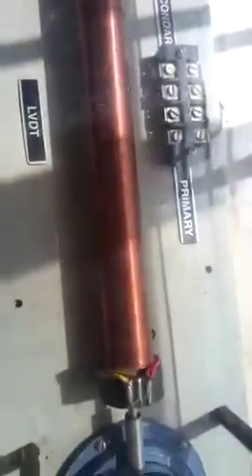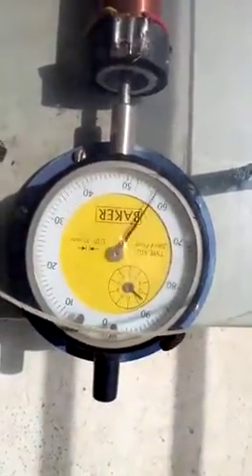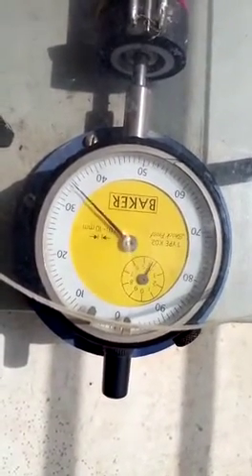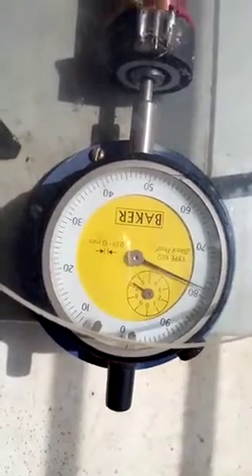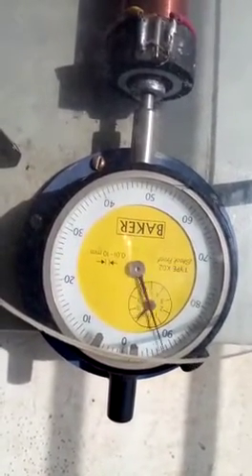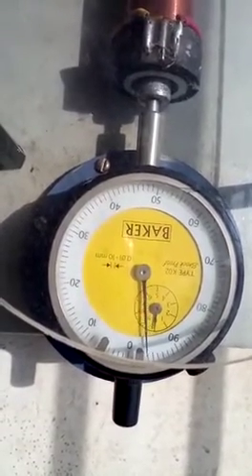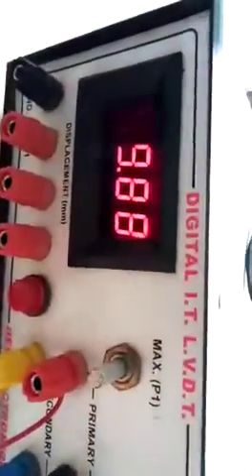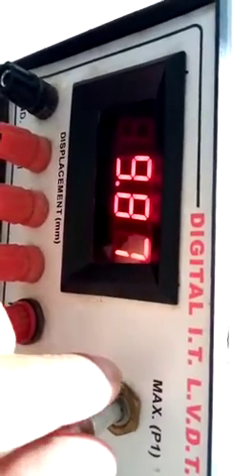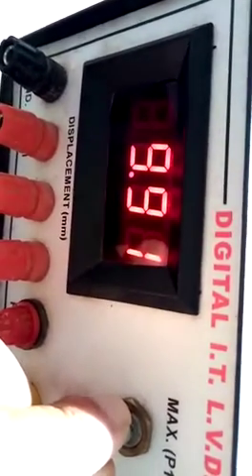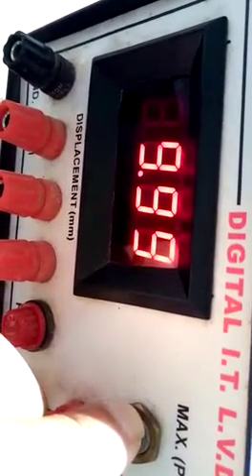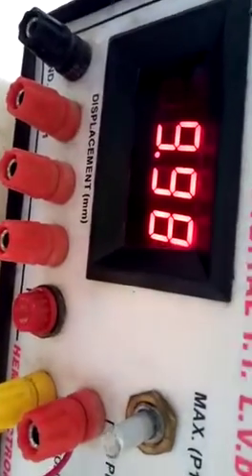Rotate the knob of LVDT in clockwise direction to displace the core in forward direction to plus 10 mm position. Now the LVDT is being rotated so that you are going to get the reading of plus 10 mm in LVDT. As you can see, it is showing 10 or near to 10 mm. If it does not indicate, use potentiometer marked maximum to adjust to 10 mm.